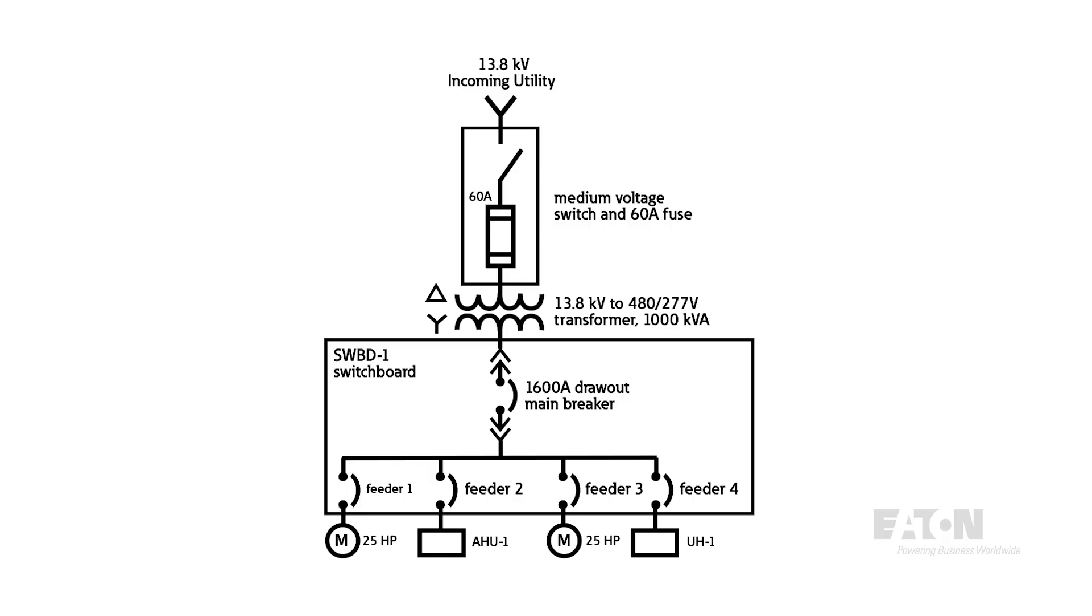Here you can see an incoming 13.8 kV utility feed labeled incoming utility. This incoming utility feed is connected to a medium voltage switch that includes a disconnect switch and 60 amp fuse. The load side of the fuse is then connected to the primary side of a 13.8 kV to 480/277 volt transformer with rating of 1000 kVA. Next, the secondary side of the 1000 kVA transformer feeds a 1600 amp draw out main breaker and a variety of fixed mounted feeder breakers, each serving a load.